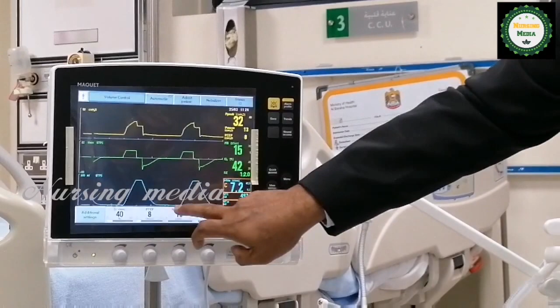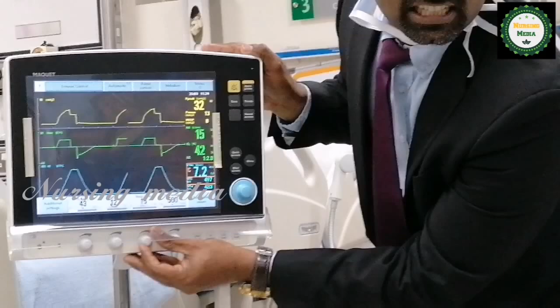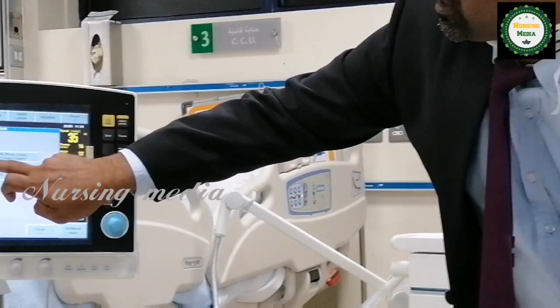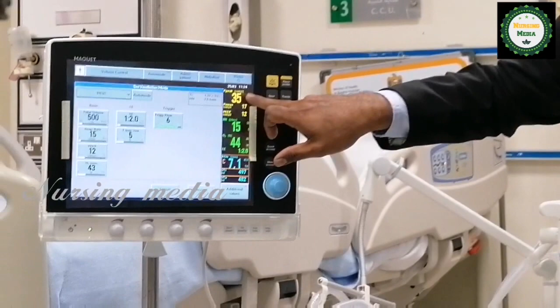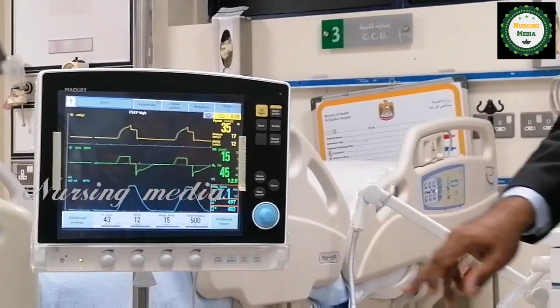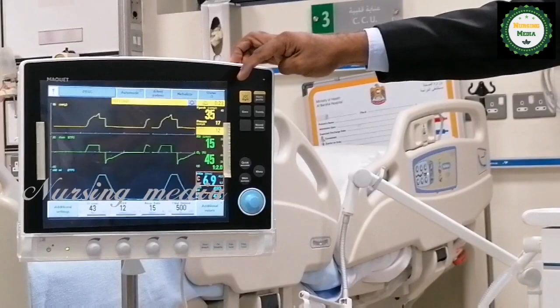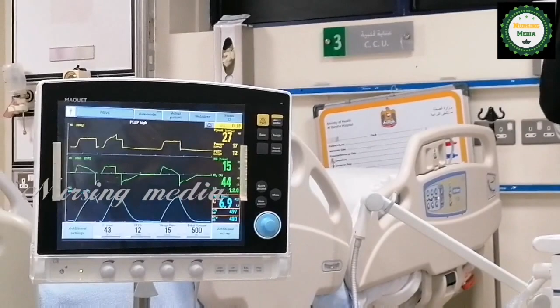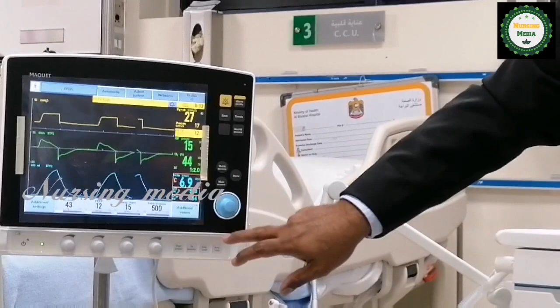Yeah. And you can control these 4 parameters directly by these knobs. Increase, decrease by these knobs. Yeah. How do you change the ventilation mode? From volume control here, you go straight away to PRVC, for example. See the same volume, 500 ml, 35 peak airway pressure in volume control. You see now PRVC, same volume. It will give a peak airway pressure at least 4 to 5 centimeters lower. It was 35, so you see now. It gives the same set tidal volume with the minimum possible airway pressure. Extremely good ventilation mode.